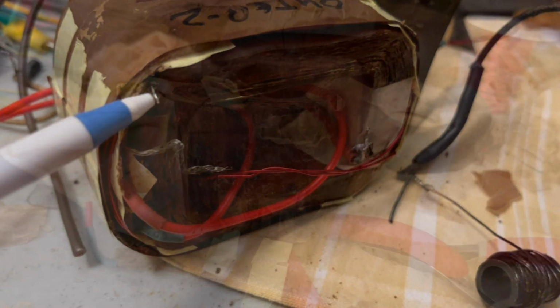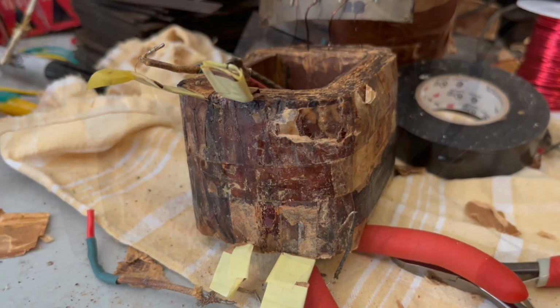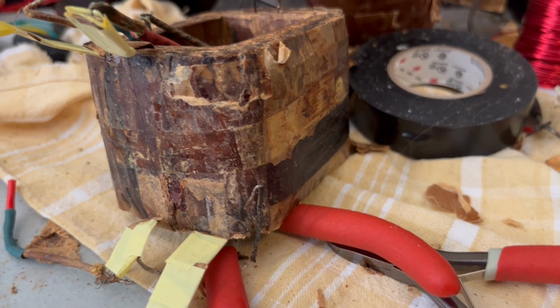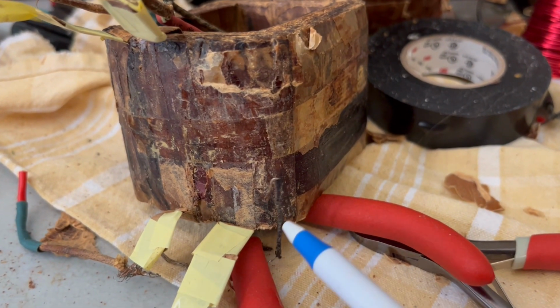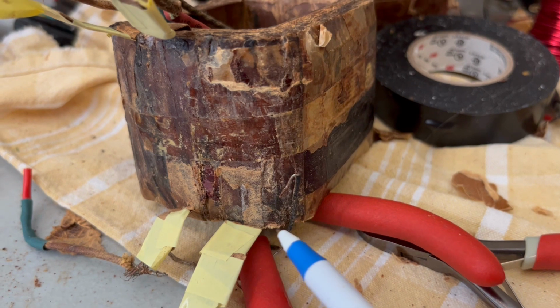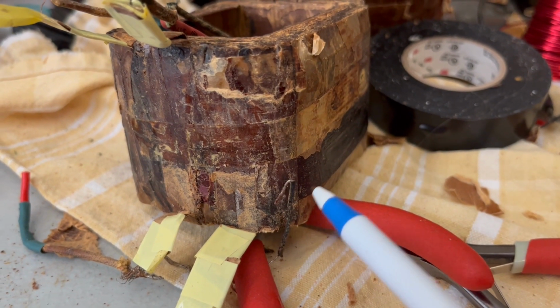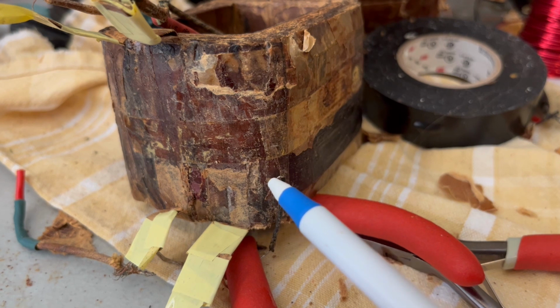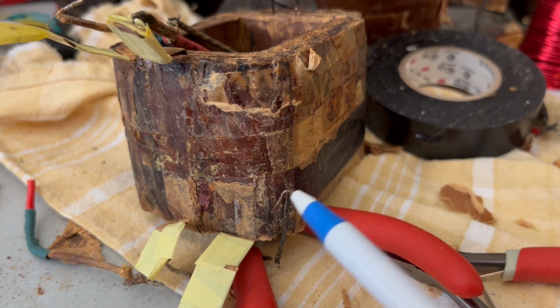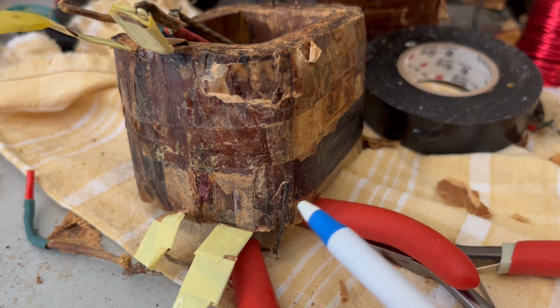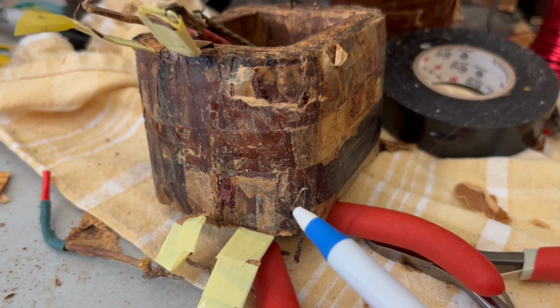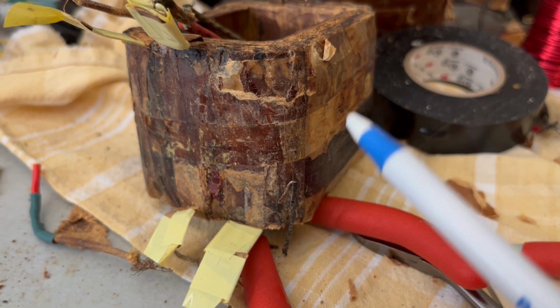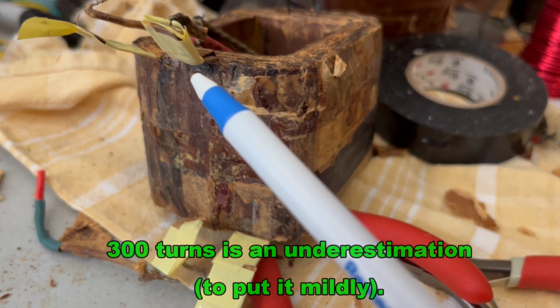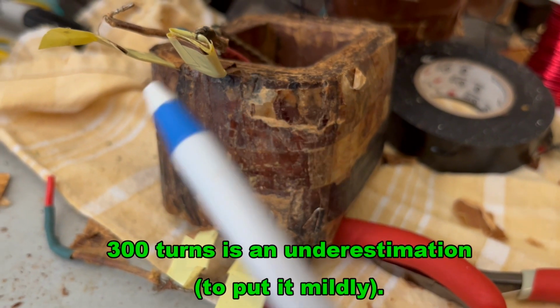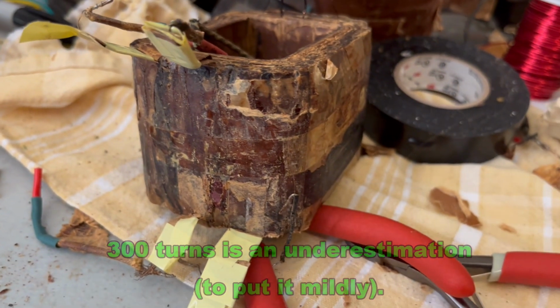Okay, so I have a worst case scenario. I wound up having to remove all of the coils in order to get down and figure out what the deal is. This is the wire right here that broke. But you can see that this is the coil wire that it's attached to. You might be able to make it out. It's as fine as a hair, if not more. But that is supposed to have about 300 turns and terminating onto either this lead or the other one. I haven't figured out which.